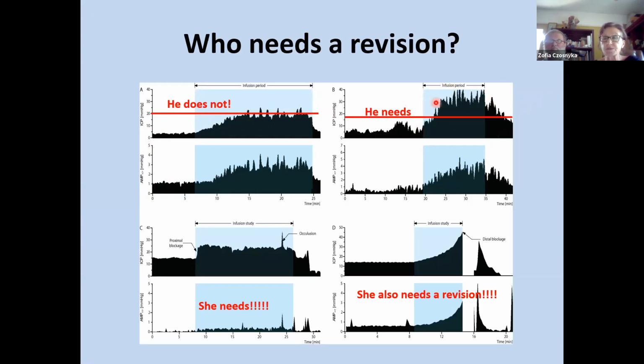Contrary to this example, in this patient the baseline is moderate, detection of pulse amplitude is okay, so the ventricular end is okay, but the response to the infusion is really excessive. So it's a strong indication for distal underdrainage or even blockage of the shunt. This is an example of proximal blockage. No detection of pulse amplitude. The shunt is draining distally. Here we've got a very steep response to the occlusion. So the shunt is draining distally, but the proximal drain is blocked, so revision is needed.